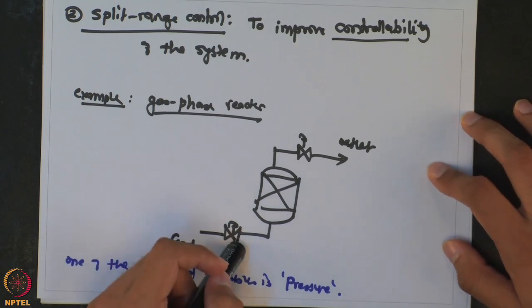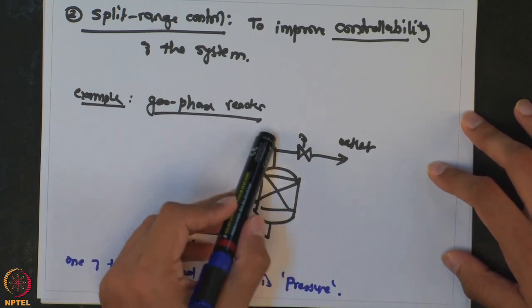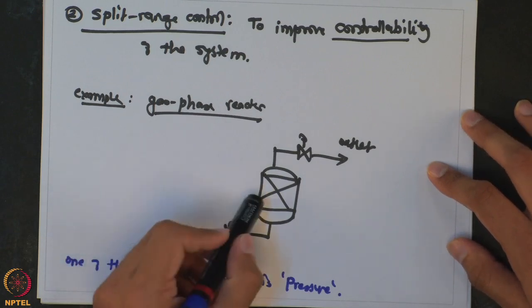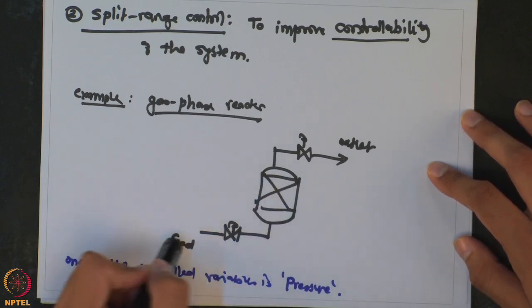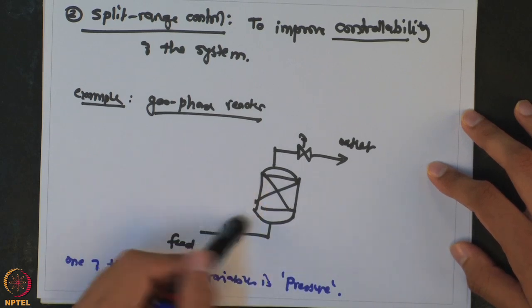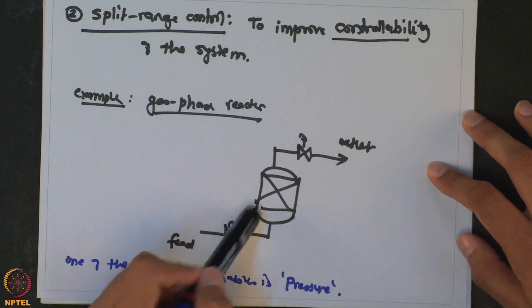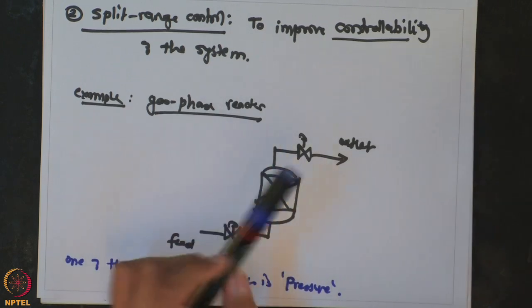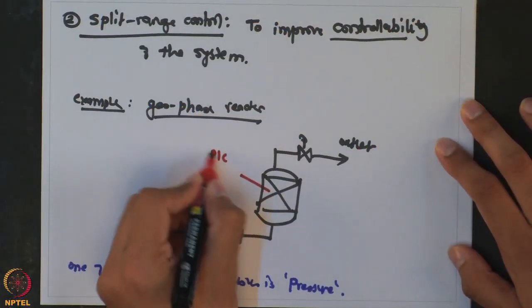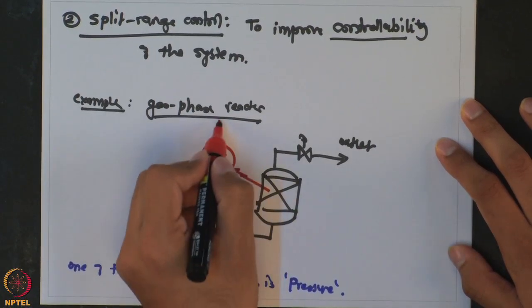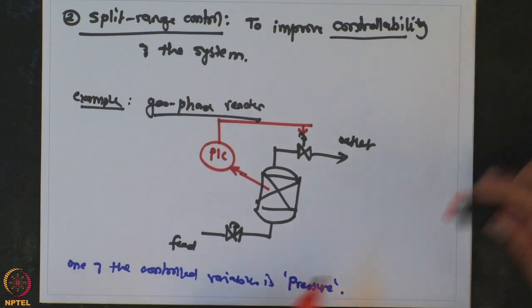Typically, when selecting pairings between input and output, you want minimal effect of pressure control on the actual operation of the process. The actual operation is the reaction, and you typically use the feed valve to control throughput — how much material is being processed. So you would typically control pressure using the outlet valve so that it does not affect reactor productivity. You have a pressure controller used to control the outlet pressure.